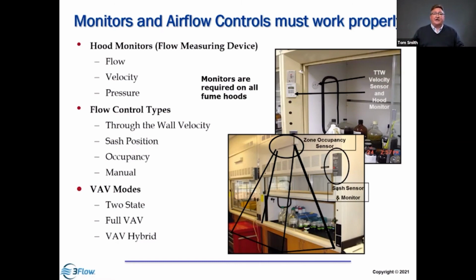And then we have to define the types of operating modes. Two-state. It's either low or high. If it's full VAV, it's modulating incrementally, maybe based on sash position. You raise it another inch, it opens up a little bit more. Raise it another inch, it opens up a little more. That's full VAV. And then you have the hybrid systems. They're modulating flow based on sash position, but they're also looking at occupancy. So when you look at the layering of these controls, the complexities, it makes the job of testing the hood that much more difficult, because now we have to confirm that it operates sash closed to sash open, occupied to unoccupied. And these require different tests to evaluate the operation.